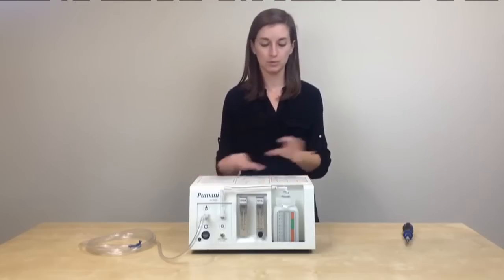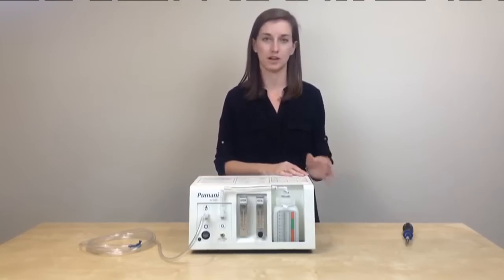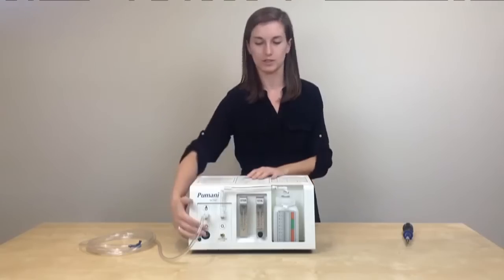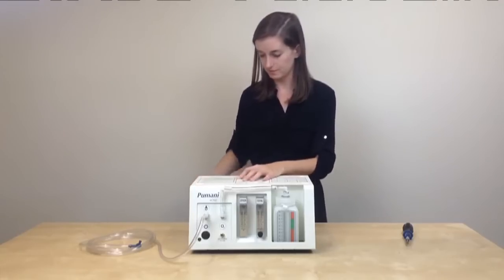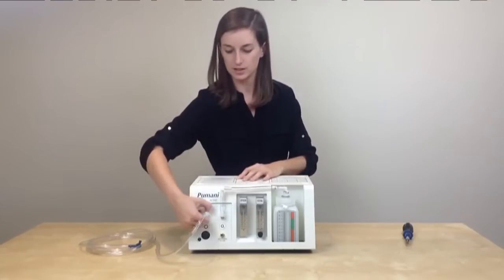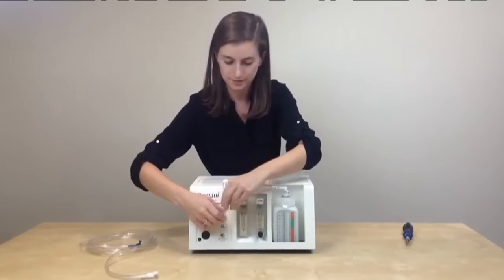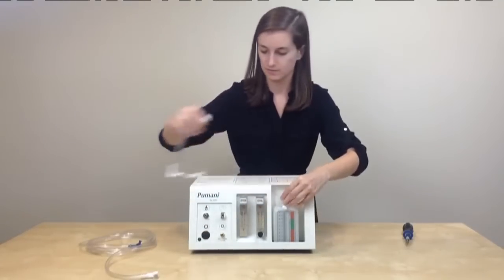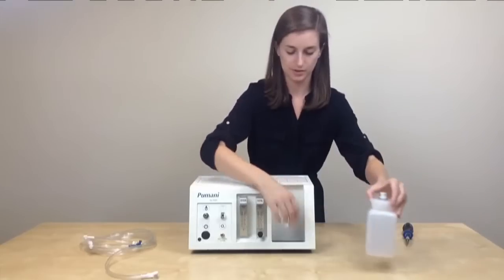So your first step should be to remove the patient from the Pumani, place them on another Pumani unit or place them on oxygen therapy, and then you'll want to turn off the unit, unplug the unit, and detach the patient tubing from the bottle tubing. And you should also remove the bottle in case the water spills.